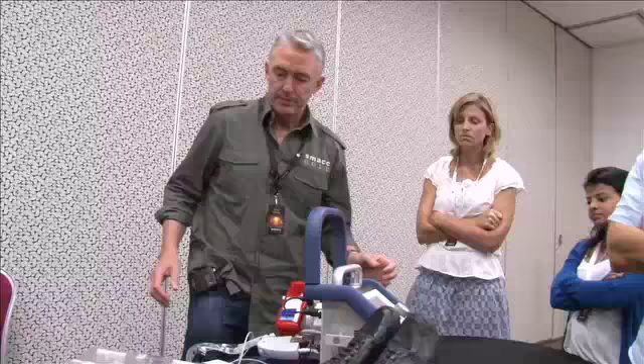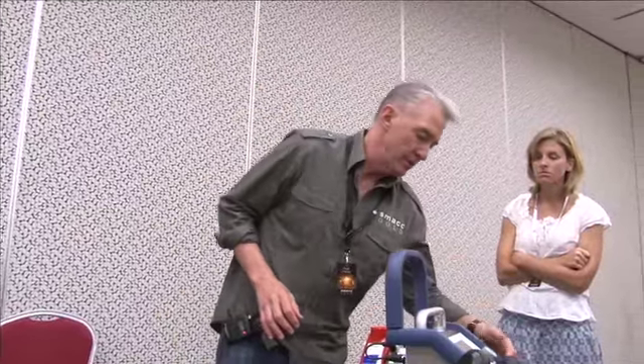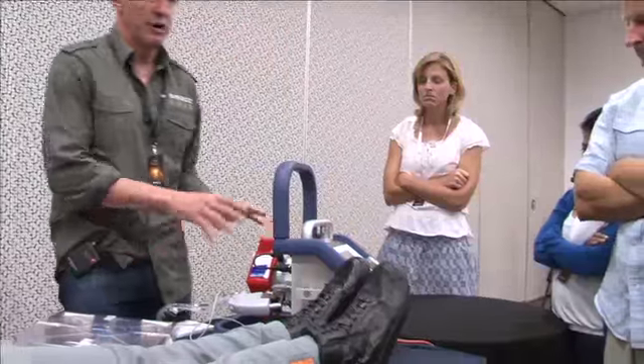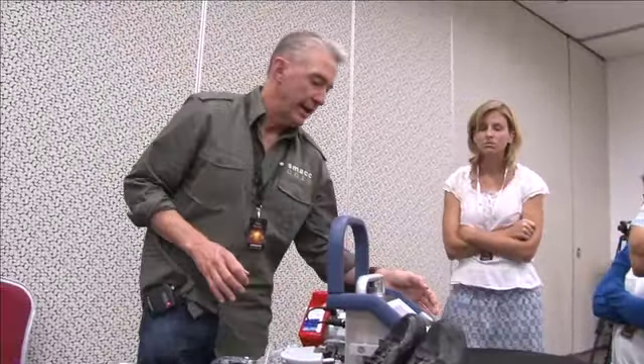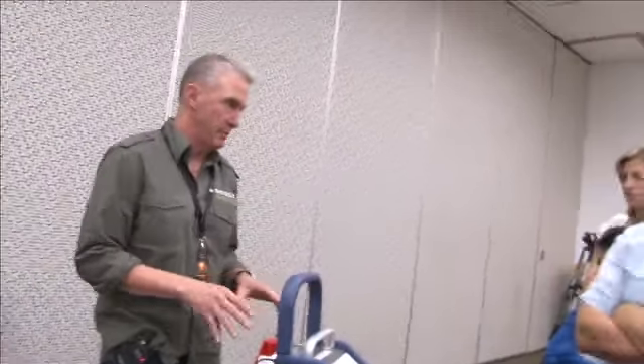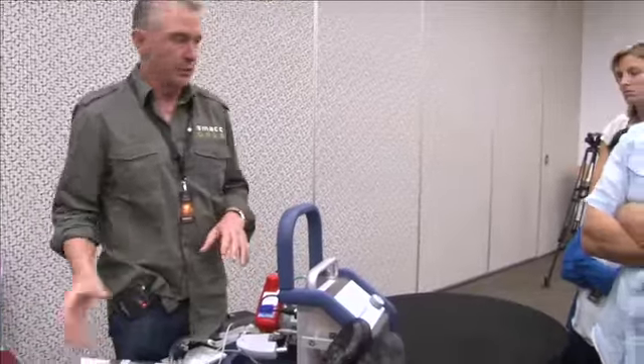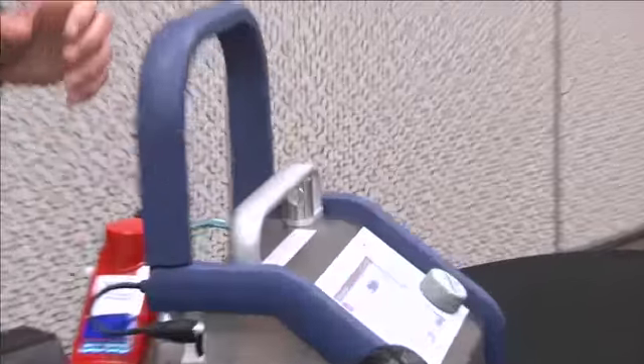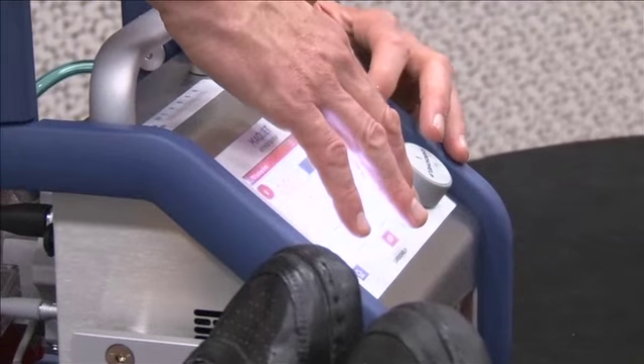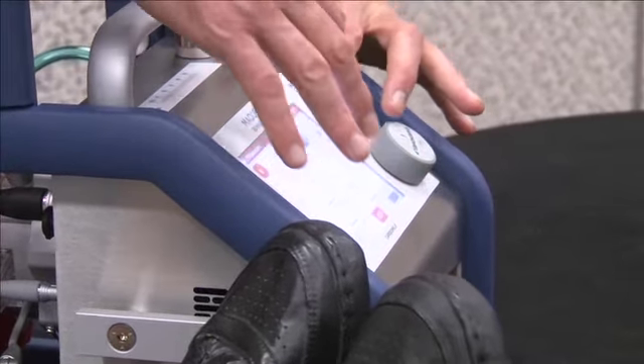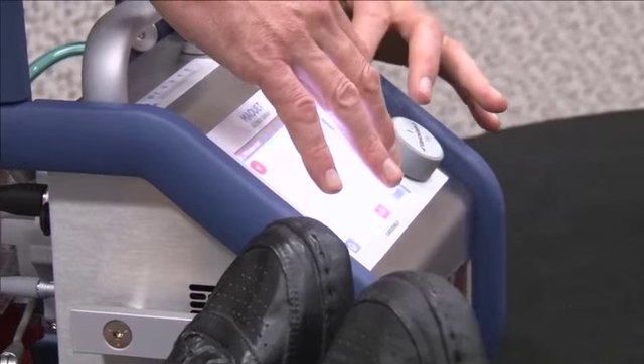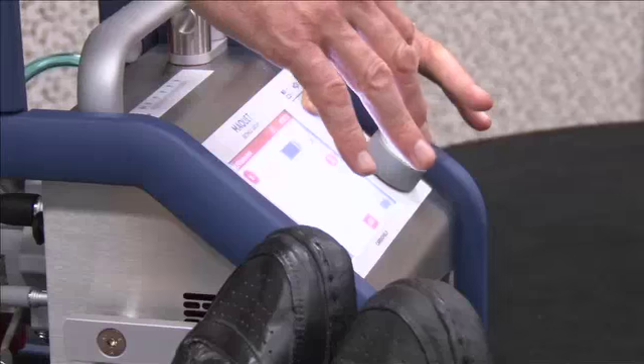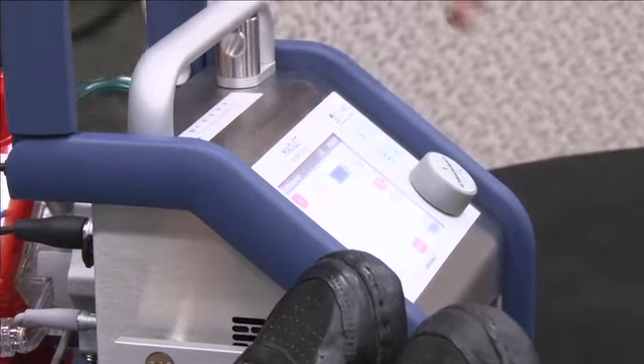So the other great feature about these pumps is that it's very easy to prime, and when we turn the pump on, we have a dry circuit initially, and the first thing we do is zero the pressures while the pump is dry. We've already done that for the last case, so I can't show you how to do that. We'll just shut these alarms up because they're very annoying. There we go. So that's overriding the alarms.